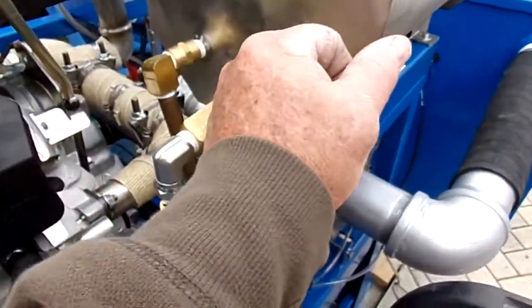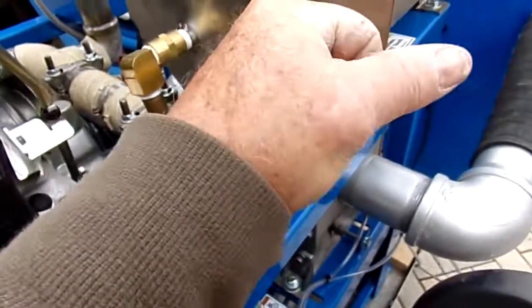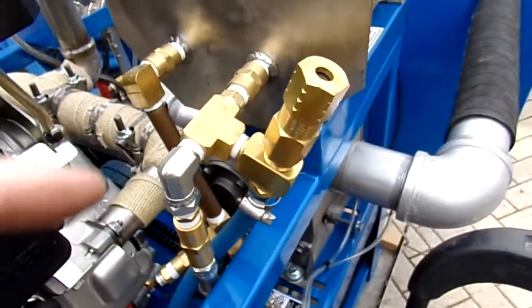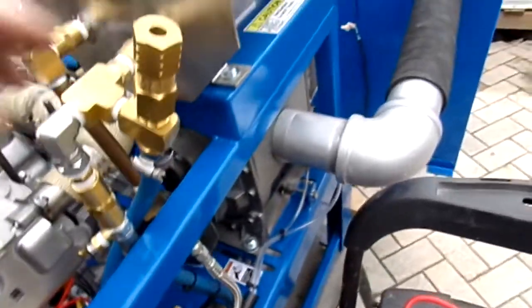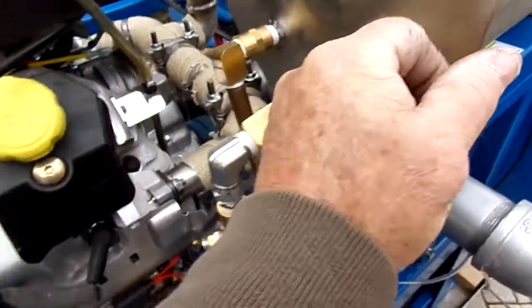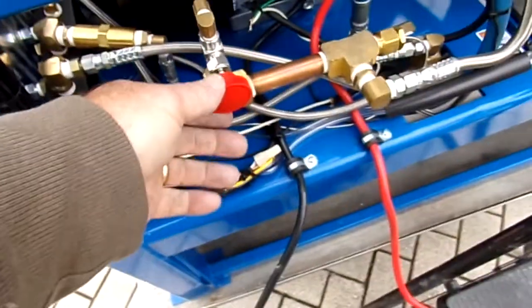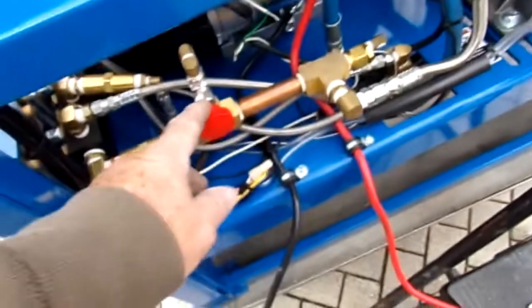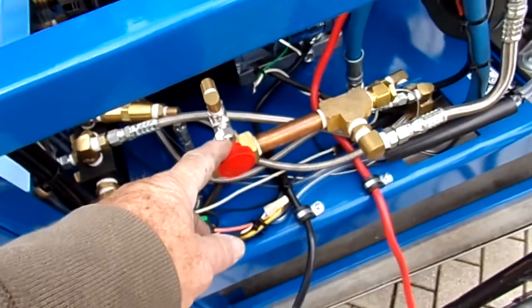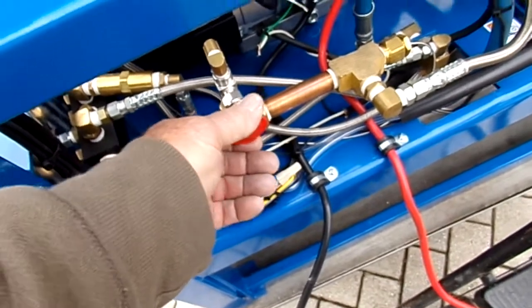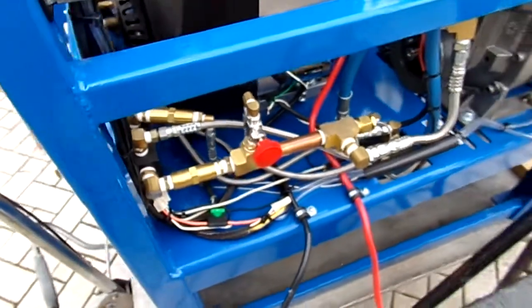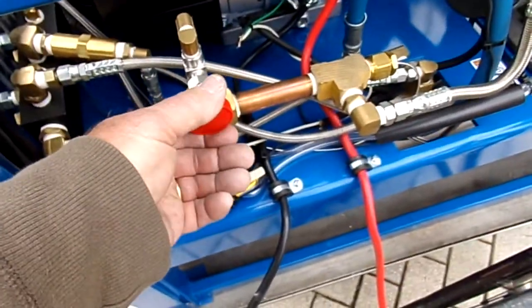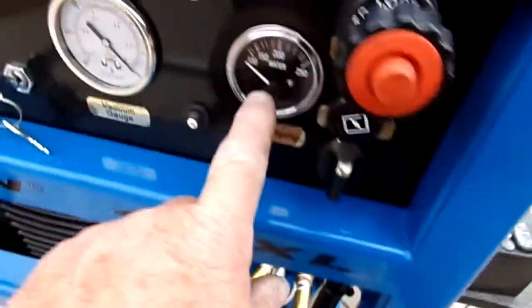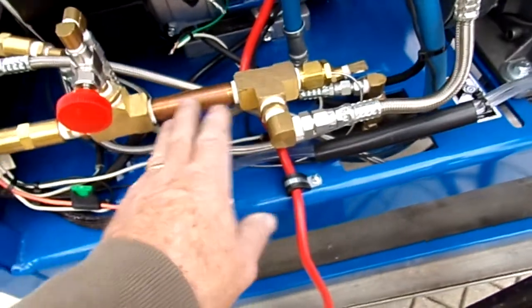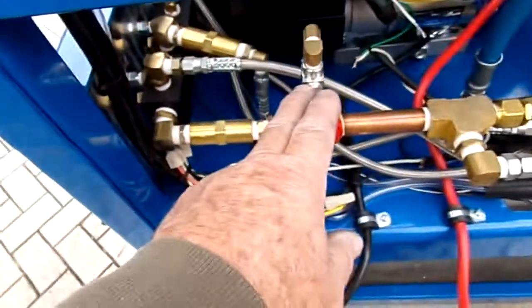This is a relief valve that usually doesn't have to be used that often. It's factory preset, but if you decided you wanted to get real high pressure, you would make sure that this was turned more clockwise. This would more than likely have to be shut off because you're going to have a bleeding effect, which will affect your top end of your pressure. So this would actually have to be turned off. But in the event that you're doing upholstery cleaning and carpet cleaning, this should always be cracked open. So you get an instant response time on your sender, so your temperature is real-time temperature, plus your reactionary time of your thermostatic probe reacts appropriately. Notice it's downstream.